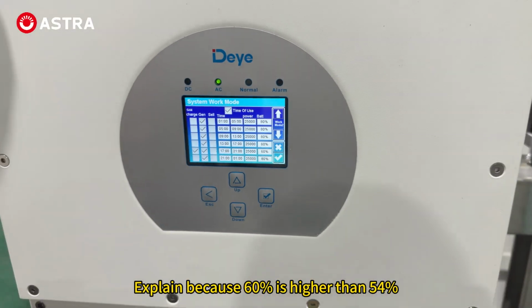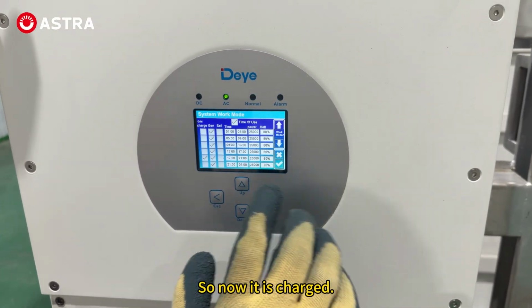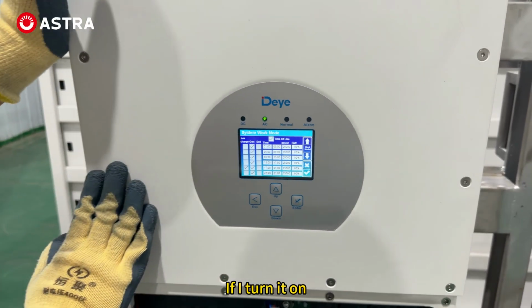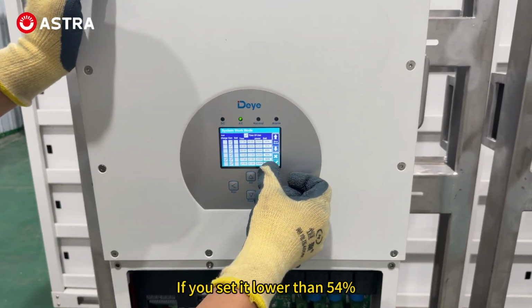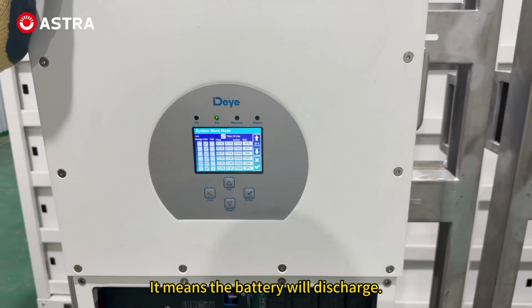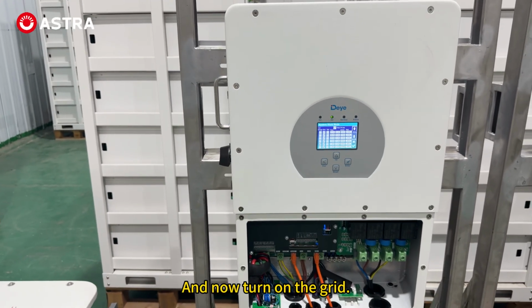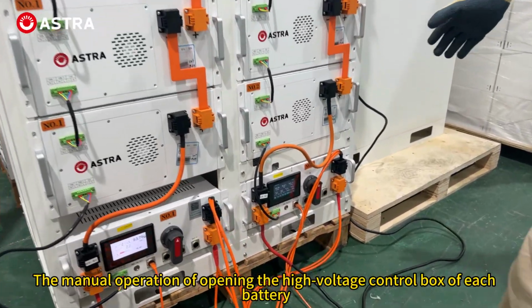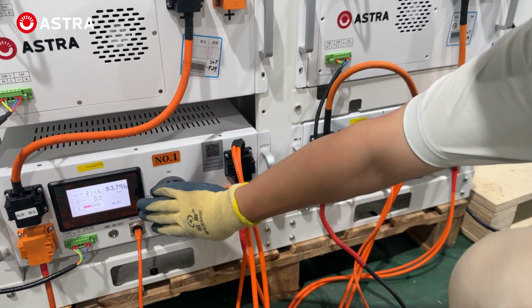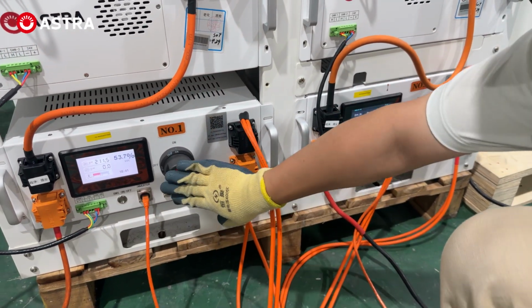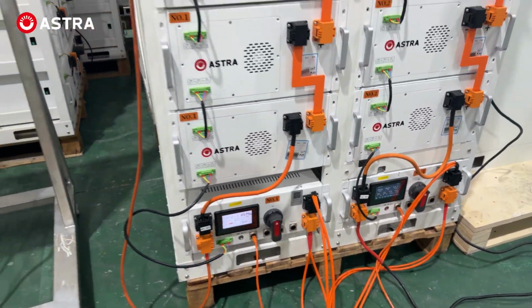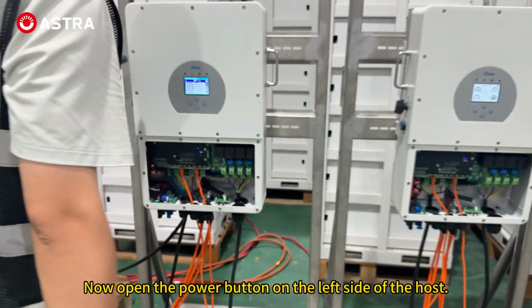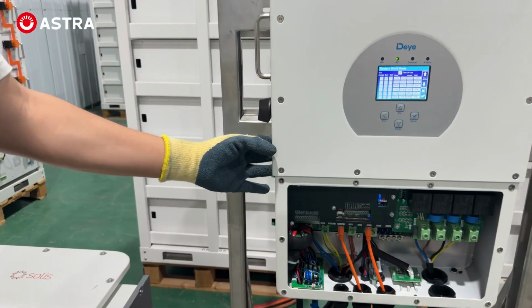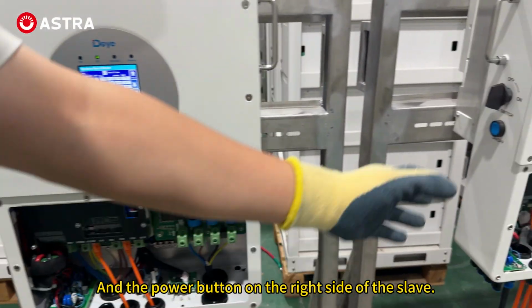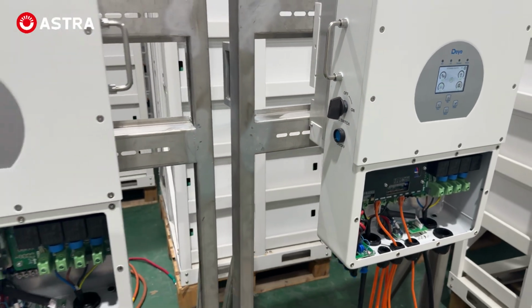Because 60% is higher than 54%, it will now be charged. If you set it lower than 54%, it means the battery will discharge. And now turn on the grid. Then manually open the high voltage control box of each battery, and power up each inverter. Now open the power button on the left side of the host, and the power button on the right side of the slave.